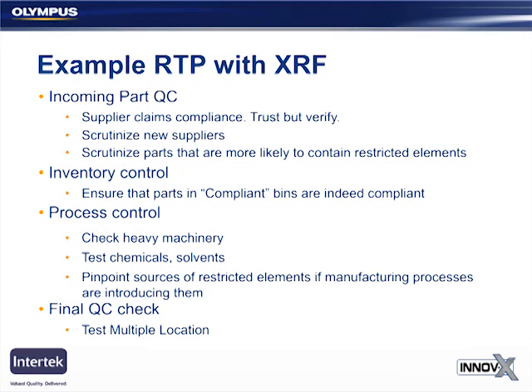XRF can be used as a final QC check, to test products before shipping. If you're manufacturing low volume production, then you may be able to test every product you send out the door by XRF. With higher volume, you may do a more random sampling. And for a larger item, a larger component, with XRF you can test multiple locations, multiple materials.